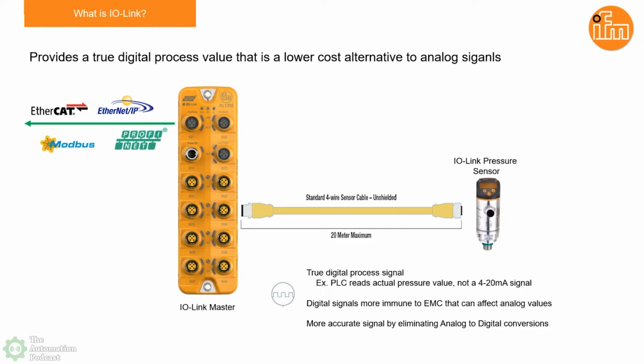In addition, because it's a digital signal, it's more immune to EMC, which typically can affect analog circuitry. So if you have EMC on a digital signal, you're less likely to have noise issues, and if there is an issue, the signal would simply drop. With an analog signal, that's different, because it doesn't have true high and low limits. If the signal is affected by EMC, it could shift by a couple of milliamps here and there, and in a process that could be critical without you even knowing it's being affected. That's why a robust digital signal is much better than an analog conversion. Also, with the digital value, you get a much more accurate signal back at the PLC, because we're eliminating many of the A-to-D conversions. So let's take a look at it a little more closely.